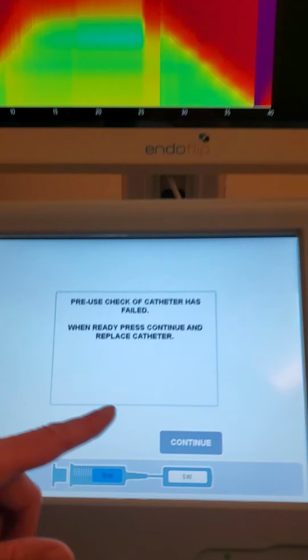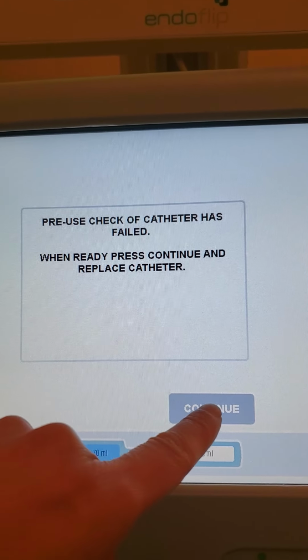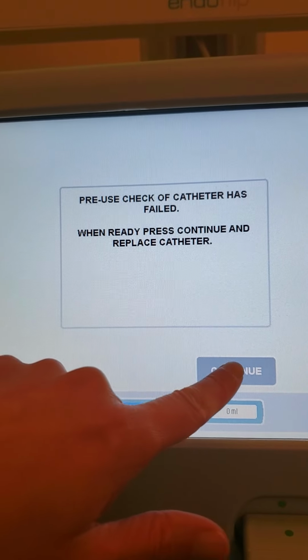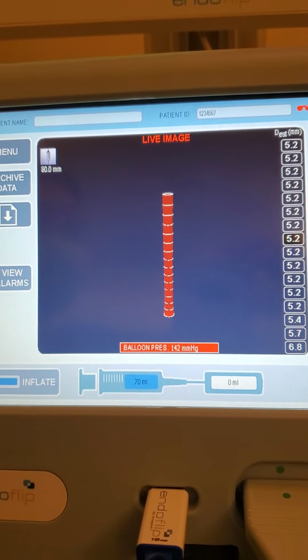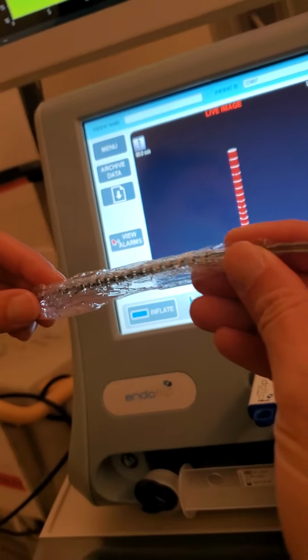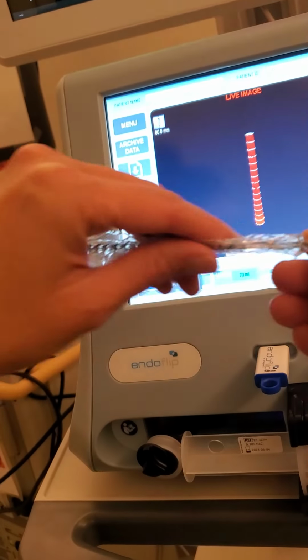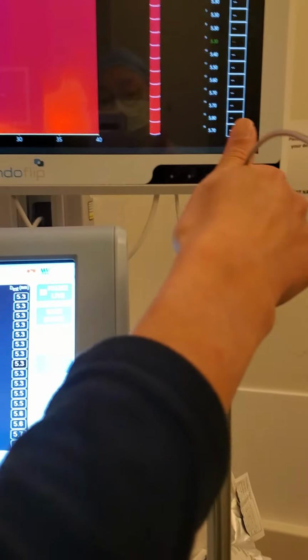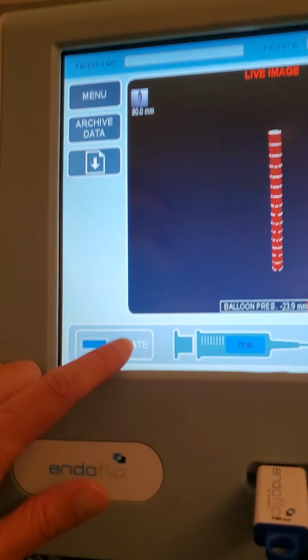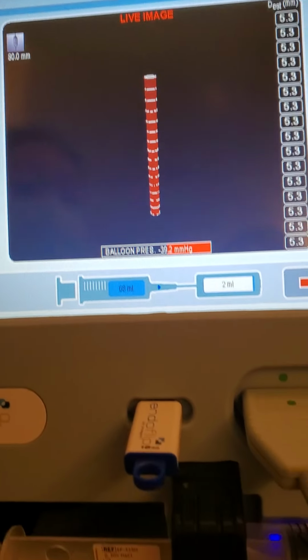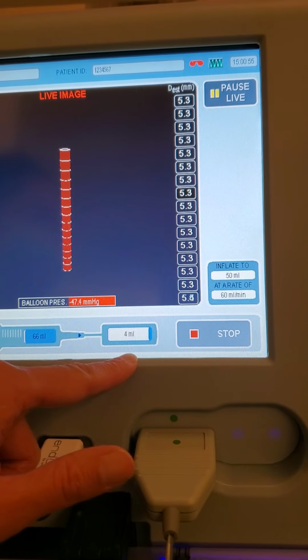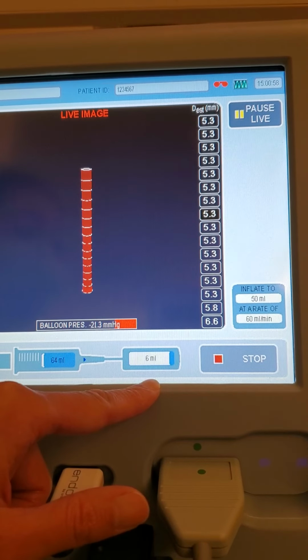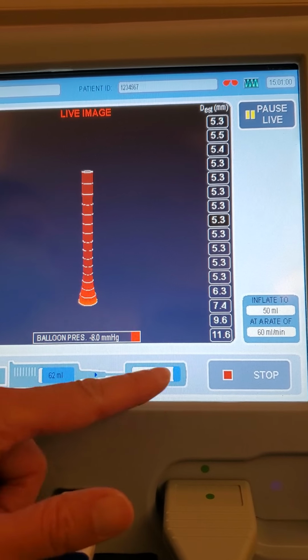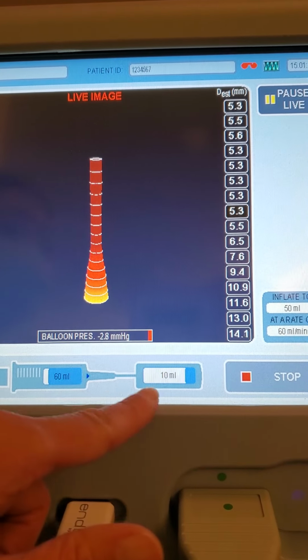Okay, so this one says it's failed. If you run into this situation, then you would try again. It could be that my demo catheters sometimes have little leaks, and that's why they send them to us as demo catheters. But if you get a case where it fails, what you would do is inflate the 8-centimeter balloon. You inflate up to 19 mLs to test it to make sure that it's still good. And the 16-centimeter balloon you would fill up to 29.